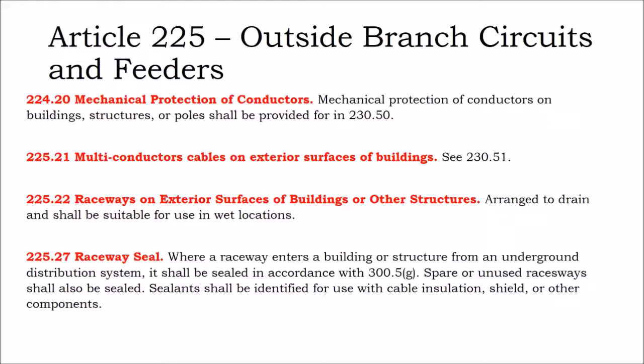And then conductors on buildings, structures, or poles require mechanical protection, subject to requirements that we still have to get to. Multi-conductor cables on exterior surfaces have different requirements. Raceways, the main thing about raceways on the exterior of buildings is that they need to be arranged to drain and be suitable for use in wet conditions. So in other words, you might have your wires coming out of your array into a box or into the roof itself. You might be going from a box into the roof.